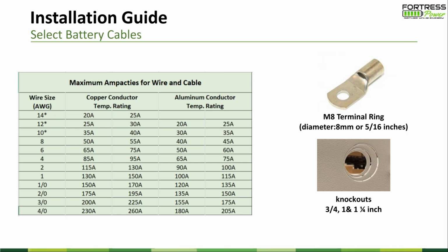So the battery, all of our batteries already have the easiest installation way, the M8 battery terminal. It's easy. You find the components in your truck most of the time. We recommend that you use the M8 terminal ring, or if you don't go with metric, then you go with inches. So we recommend 5/16 inch battery lug. That works perfectly. For the knockouts, we have 3/4, 1 inch, and 1 1/4 inch knockouts. It depends what conduit you want to use.